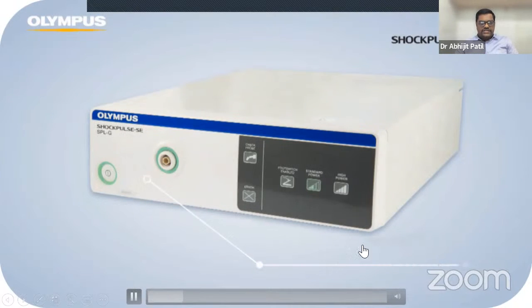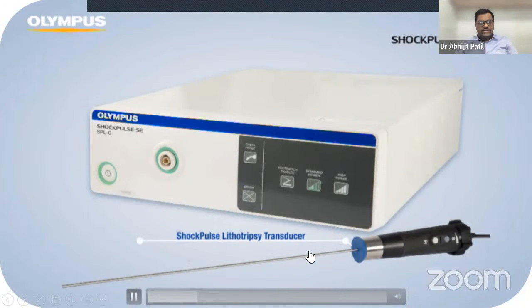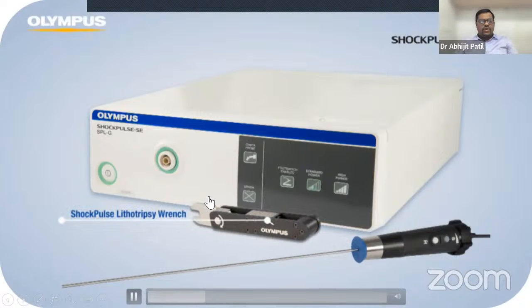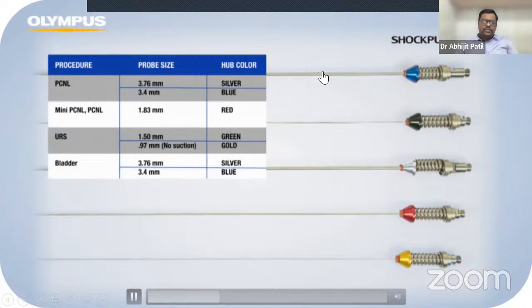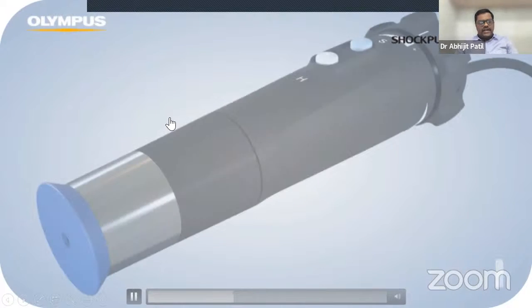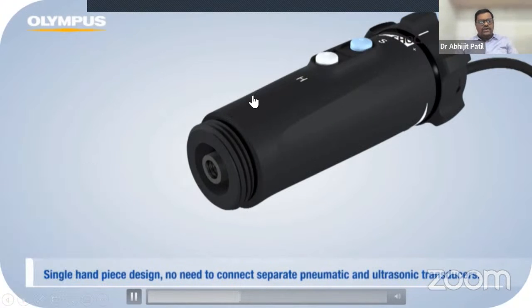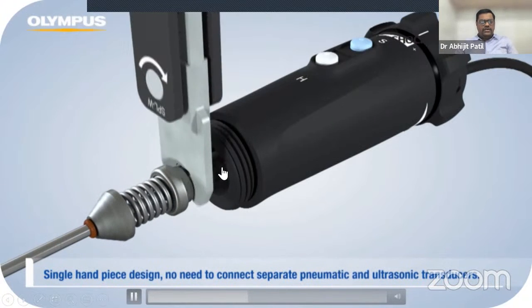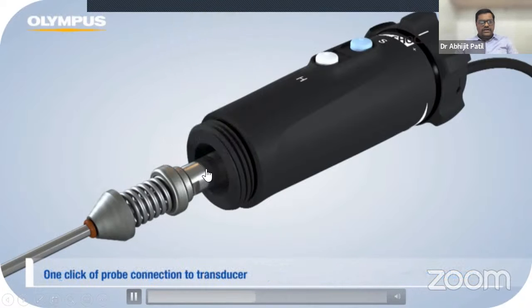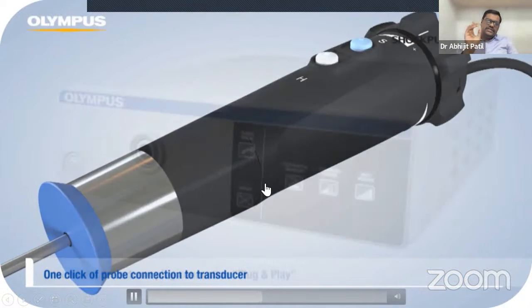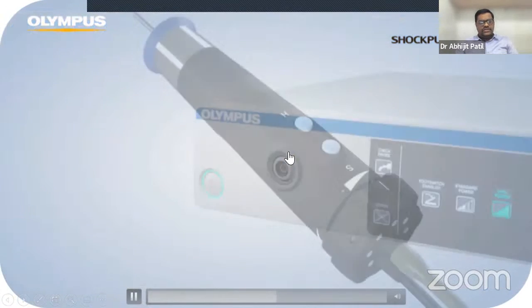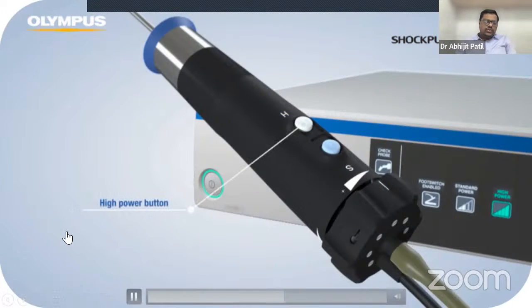It has its own generator. Then it has its own handpiece, also known as the transducer. Then it has its own torque wrench for tightening the probe. These are the probes. For mini PCNL you have 1.8 mm, in Trilogy it was 1.9, and for standard it was 3.4. Now you can attach the probe as can be attached in Trilogy, and you can attach the cable to the generator as shown in this video. So there are two buttons.